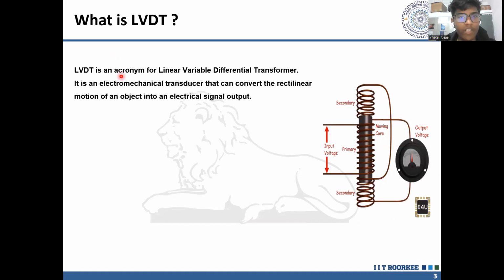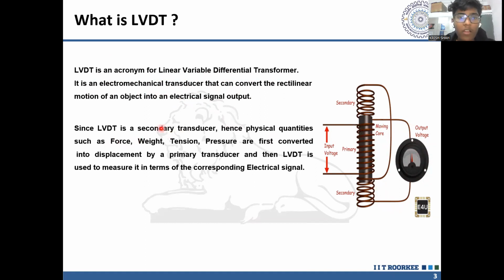Let us understand what LVDT is. LVDT is an acronym for Linear Variable Differential Transformer. It is an electromechanical transducer that can convert the rectilinear motion of an object into an electrical signal output. Here the object is the moving core, and it is being checked by the output voltage, which is an electrical signal. The LVDT is a secondary transducer. What do you mean by secondary transducer? Inputs such as force, weight, tension and pressure are first converted into a displacement by a primary transducer, and the displacement is then measured by the LVDT. So LVDT is a secondary transducer.